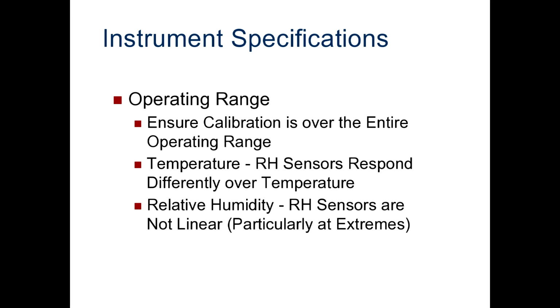It's important to look at the temperature. RH sensors respond differently over temperatures, so it's important that they get calibrated over the operating temperature range as well as humidity range. And RH sensors are not linear, particularly at the extremes. So if one were to calibrate, say, between 20 and 70%, yet operate at 10 to 80, you could get some surprises at those extremes.